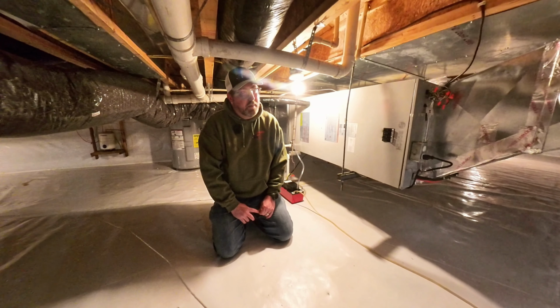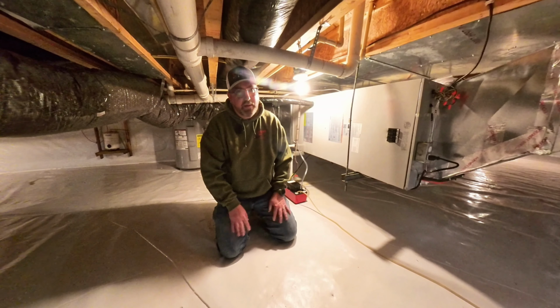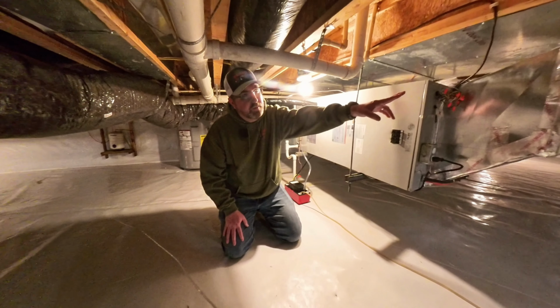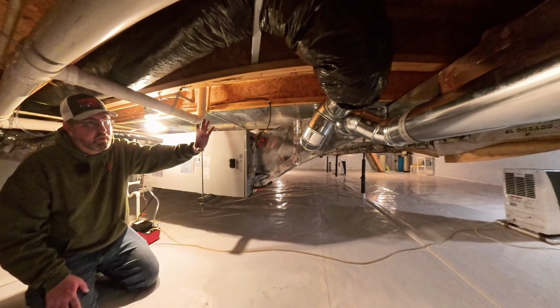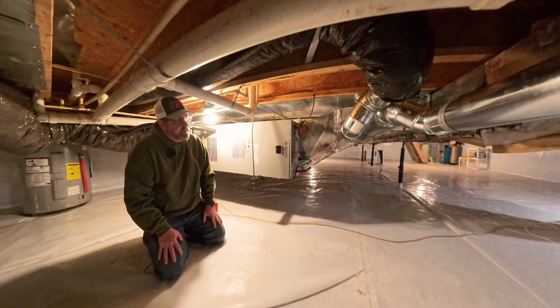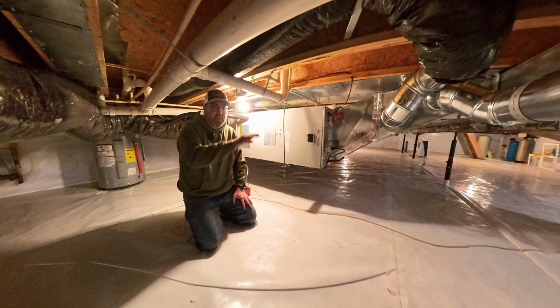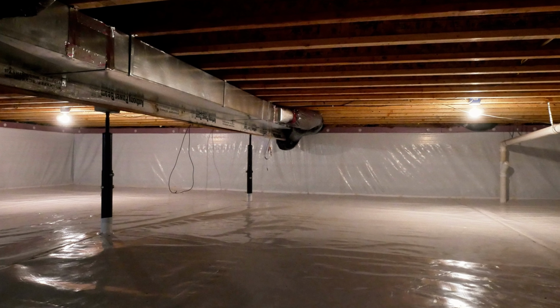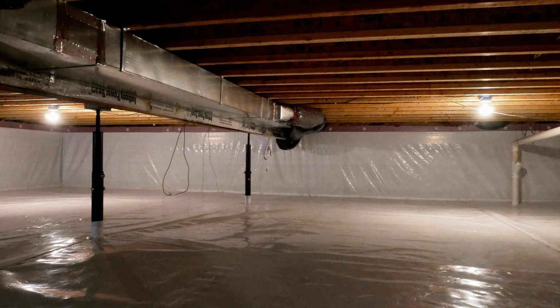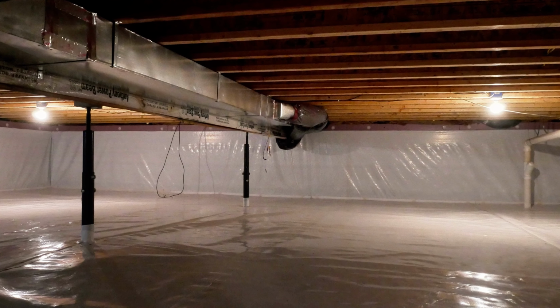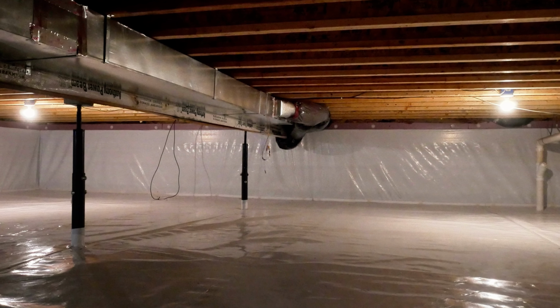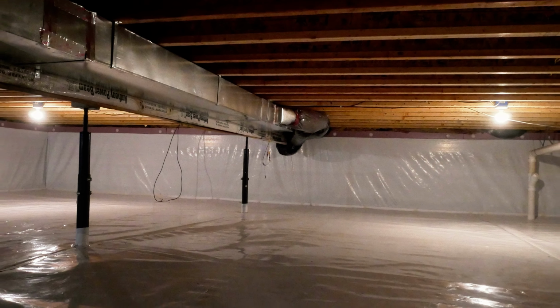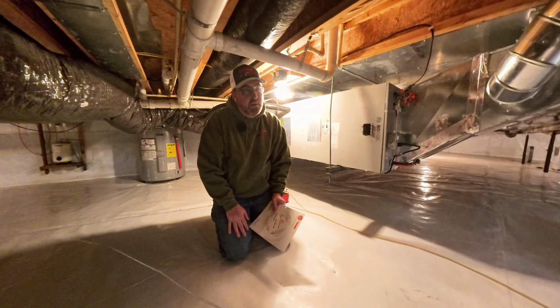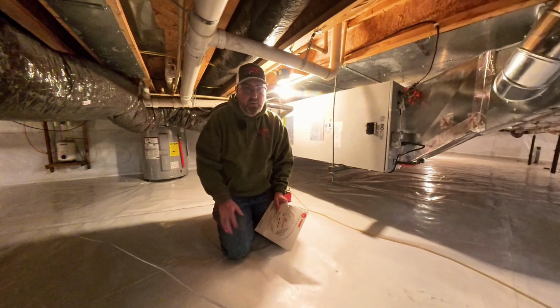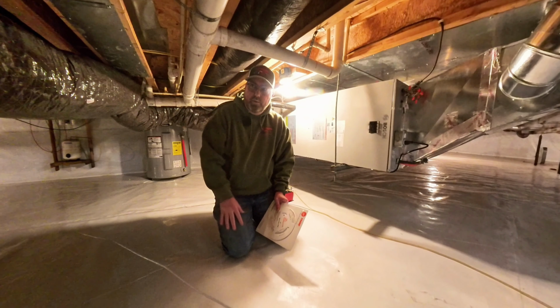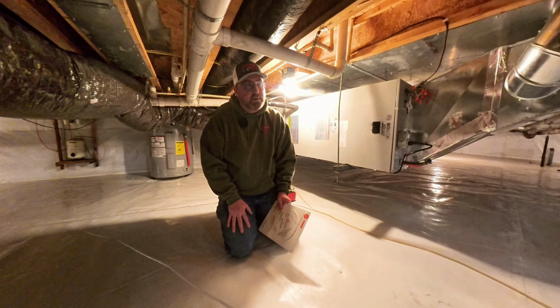So along with moving some of the supply runs out of the end cap, we added 2 from the house that were already here to the supply plenum so that we could relieve the supply duct that runs down this other direction. That supply ducting is only sized to carry so much airflow, and it was already overloaded.